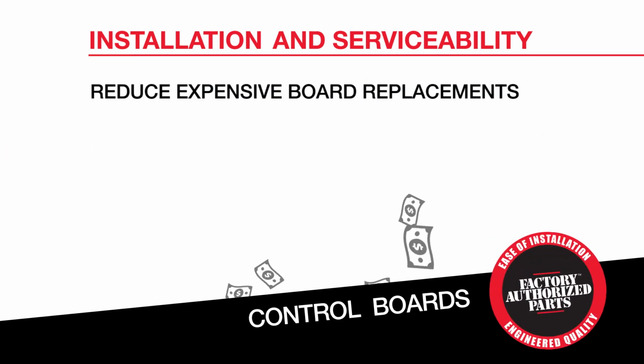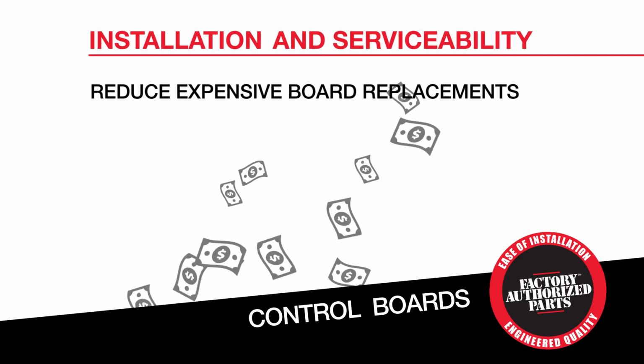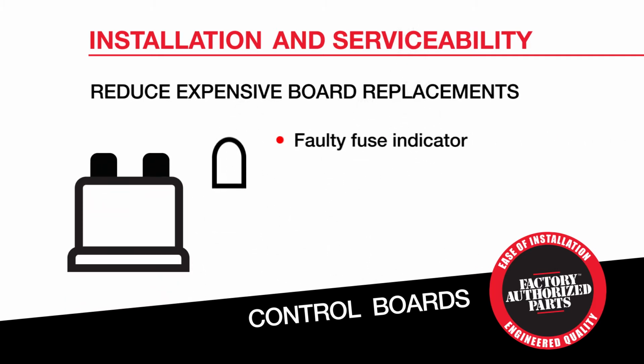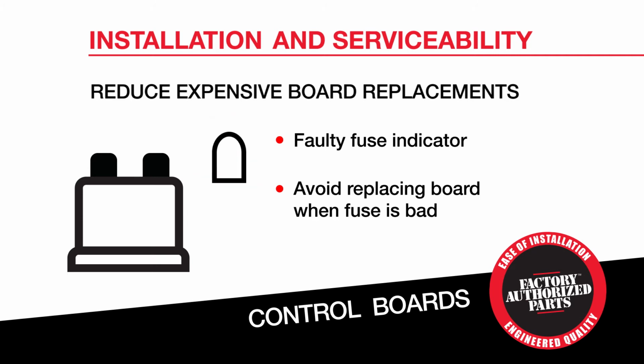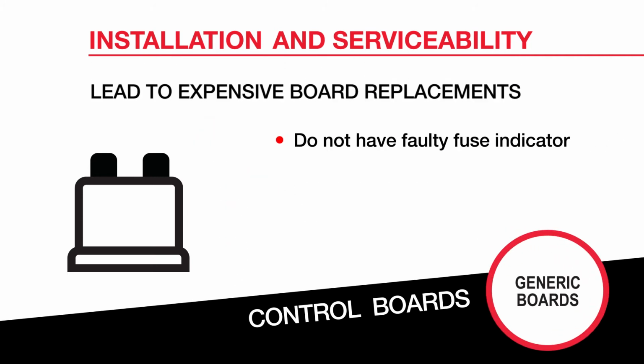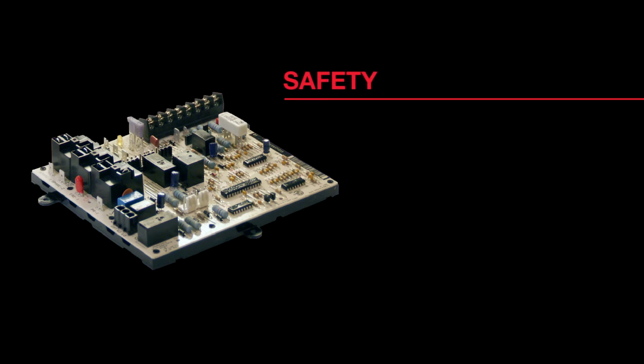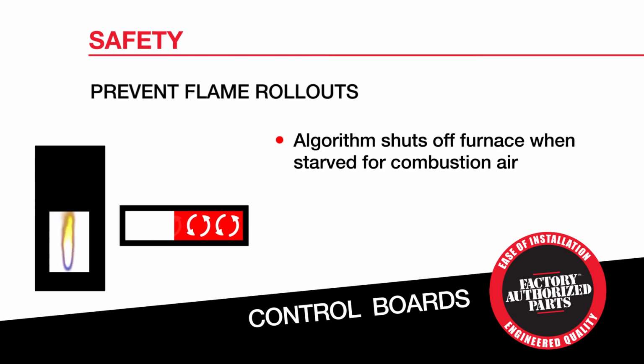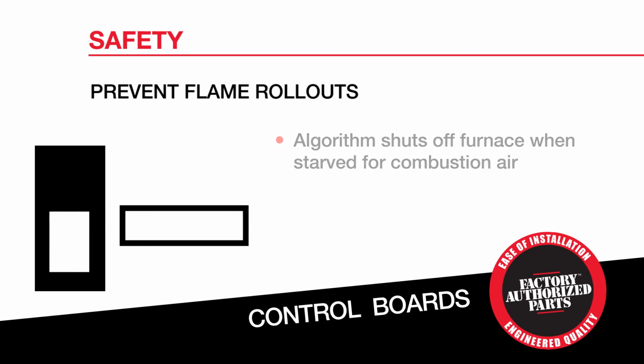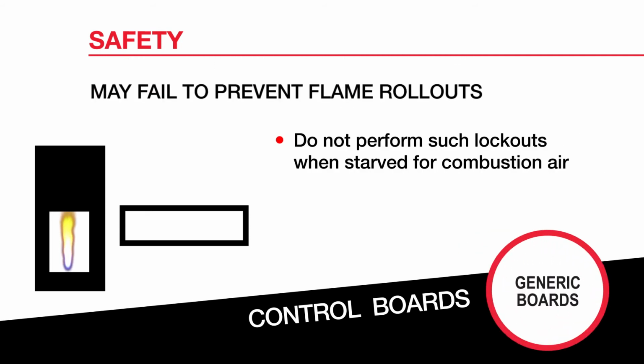You'll also reduce expensive board replacements when you use factory authorized parts control boards. They feature a faulty fuse indicator, so you can avoid replacing the whole board when only the fuse is bad. Some generic boards do not have an indication for a faulty fuse, and this can lead to more control board replacements. And the fourth reason to choose factory authorized parts control boards is safety. Factory authorized parts control boards have a flame rollout detection algorithm that shuts off the furnace when it's starved for combustion air. This is a great safety precaution since this feature prevents flame rollouts. Some generic boards may fail to prevent a flame rollout because they don't perform such lockouts.